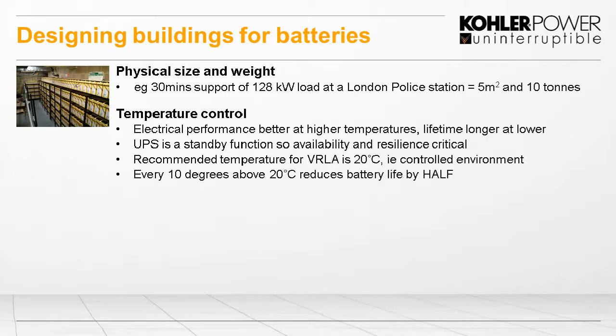Temperature control is another very important consideration for the batteries and for the UPS to some extent. A typical battery, the VRLA, which is the lead-acid valve-regulated batteries, have a recommended temperature of 20 degrees. The battery will perform better at higher temperature, but their lifetime will be lower. Every 10 degrees above 20 degrees, their lifetime will halve. So it's quite critical that we keep these as close to the 20 degrees as we can. Below 20 degrees, the batteries won't age quicker, but they will not have the performance that we would have at 20 degrees.